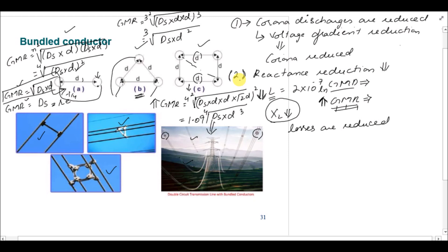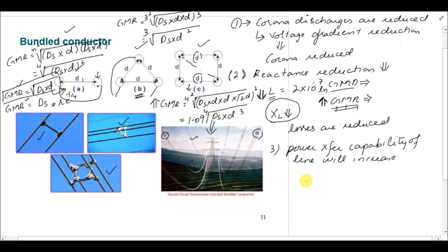The third advantage is that the power transfer capability of the line will increase. The power transfer formula for a transmission line is P = (E1 × E2 × sin δ) / XL, where δ is the transmission angle, E1 is the sending-end voltage, E2 is the receiving-end voltage, and XL is the line reactance. So if XL is reduced, then the power transfer capability of the line is increased.